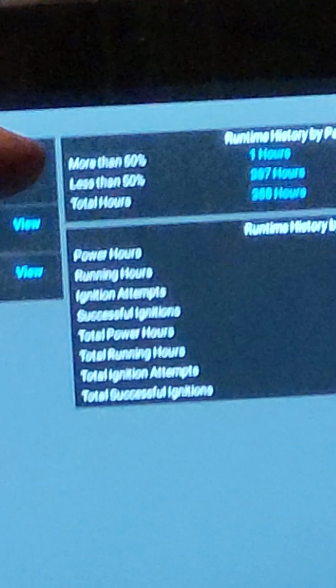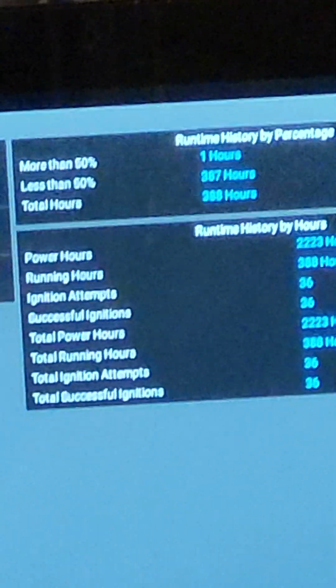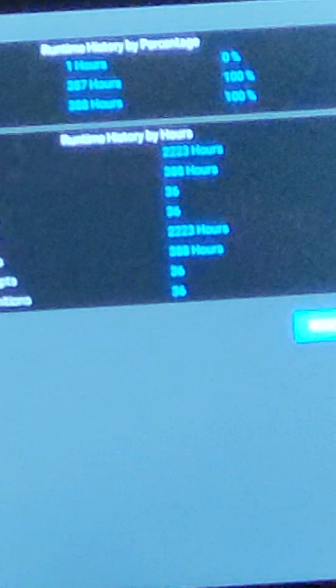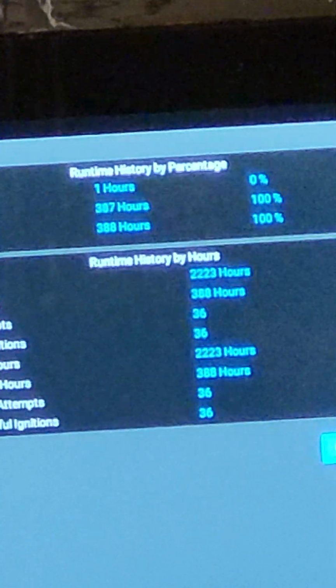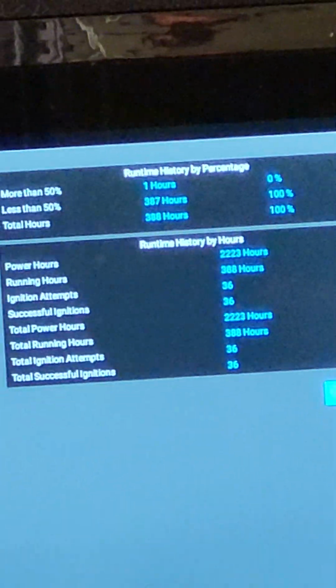Also here, this is a good screen. It also tells you your runtime. So how many hours you've got of runtime more than 50% firing rate, and then how much runtime less than 50% firing rate. Right now you've got 388 hours of runtime. 387 hours are less than 50% firing rate. So that tells you that you've got more than enough boiler, and the demand, it's not running all the way at 100%.